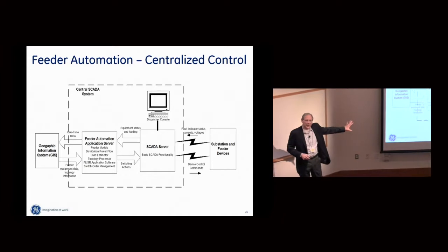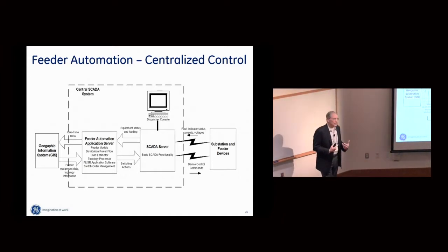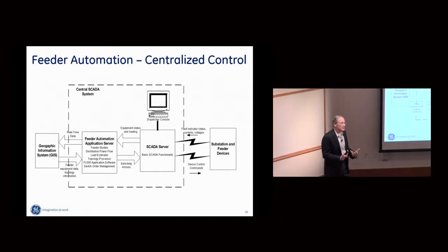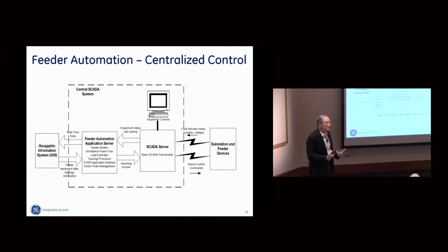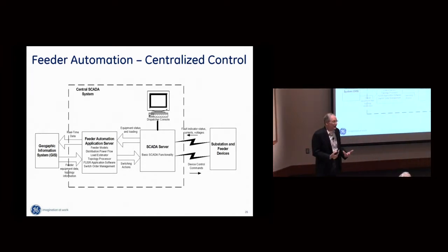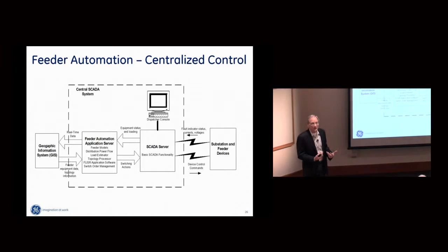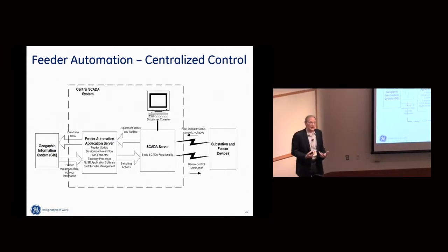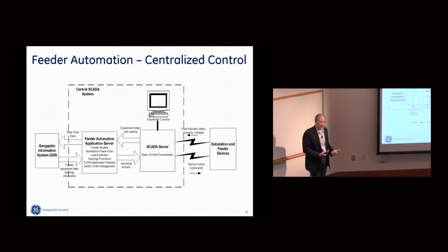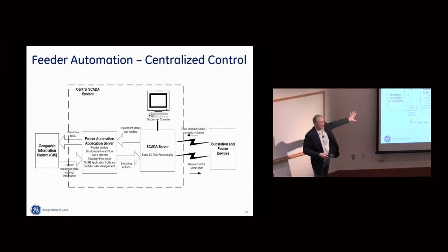This takes some time to implement. So if I were a utility starting on this, I would put logic right away in my substation to do fault detection, isolation, restoration, as well as VOLT/VAR control, because I could realize benefits quickly at the substation level. And while I'm doing that, I would begin implementation of a centralized approach.